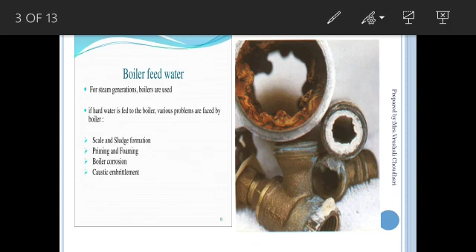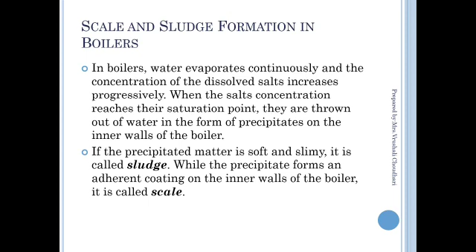What is scale and sludge formation in a boiler? When we heat the water in a boiler, water gets evaporated continuously. As the concentration of the dissolved salt increases progressively, whatever minerals are dissolved in the water increase in concentration, because these salts do not evaporate, so they settle down on the surface of the inner walls. We observe a deposition in the form of precipitate on the inner wall of the boiler. If this precipitate is soft and slippery, it is called sludge, while if the precipitate is hard and sticks as a coating on the inner wall of the boiler, it is called scale. If it is soft and slippery, it is called sludge. If it is hard, it is called scale.